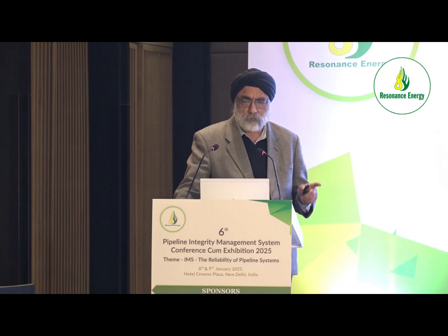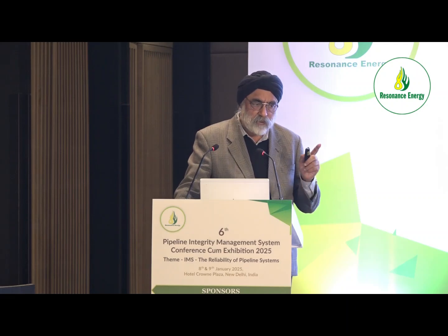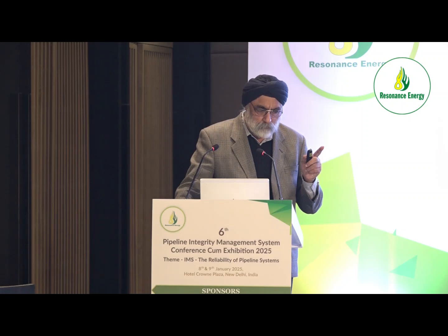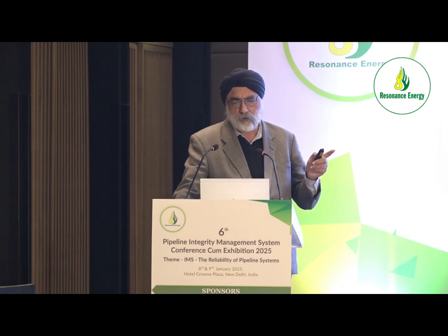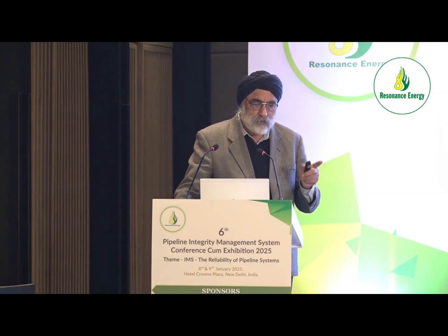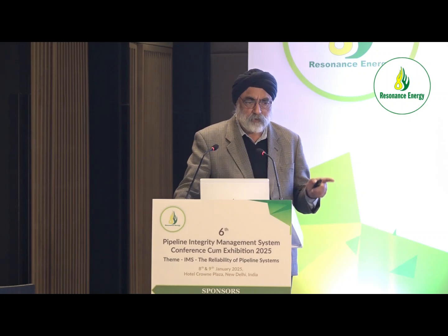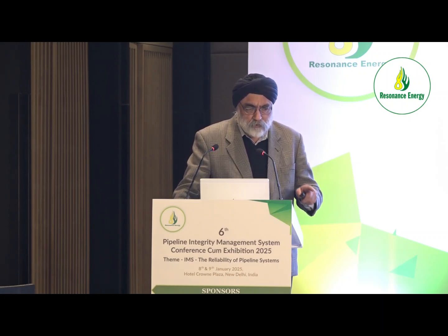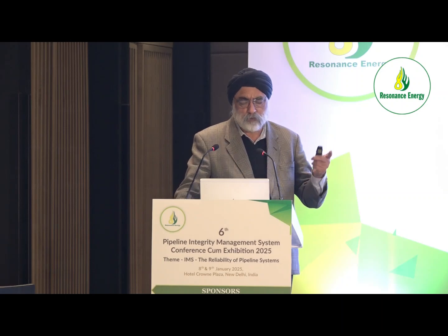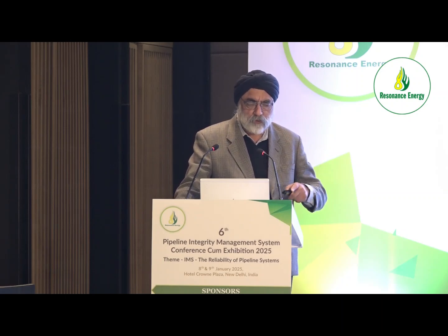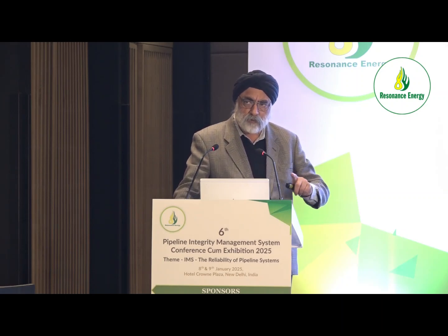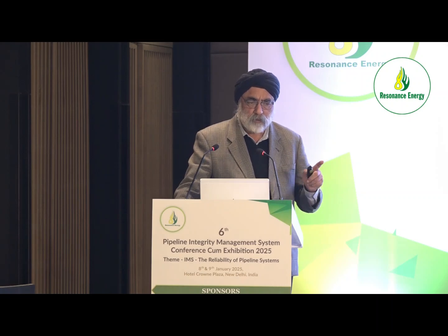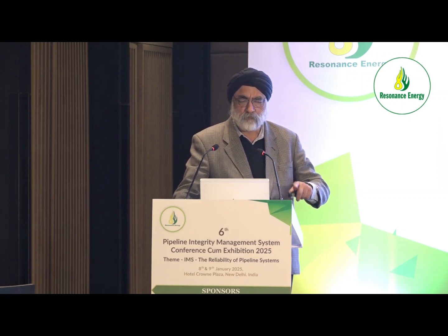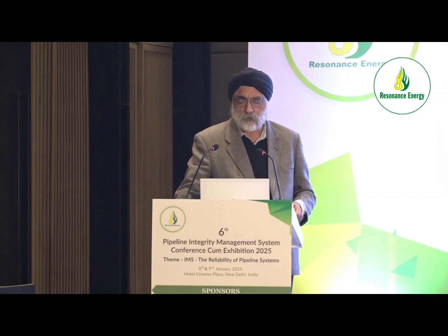But what we will now be seeing is the solar plants and solar PV panels which we are putting in, anything above 1 or 2 megawatts. The DC side is causing a lot of milliampere currents to flow into the ground, which is a part you can't avoid. If our pipelines are very close to it, then there is an interaction between the leakage current which will be picked up by the pipeline, and whenever it gets discharged, we'll have rapid corrosion.